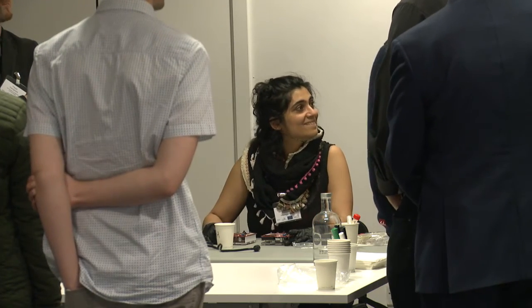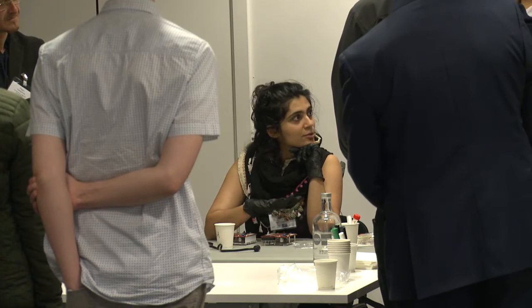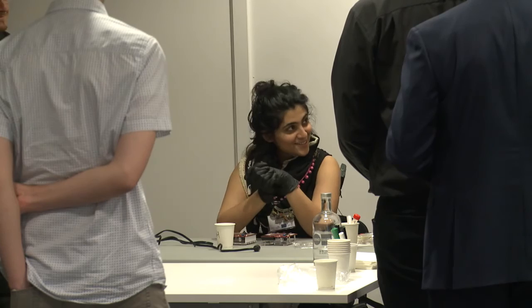Question: do you need 90 volts at least for each of those? We're using more here because I'm not going to operate with a top plate, so we're going to use 250 volts. Oh, sorry, I'm covering this one. It looks like a lot. If I touch it, what happens? Well, if you have a good insulator, nothing will happen.